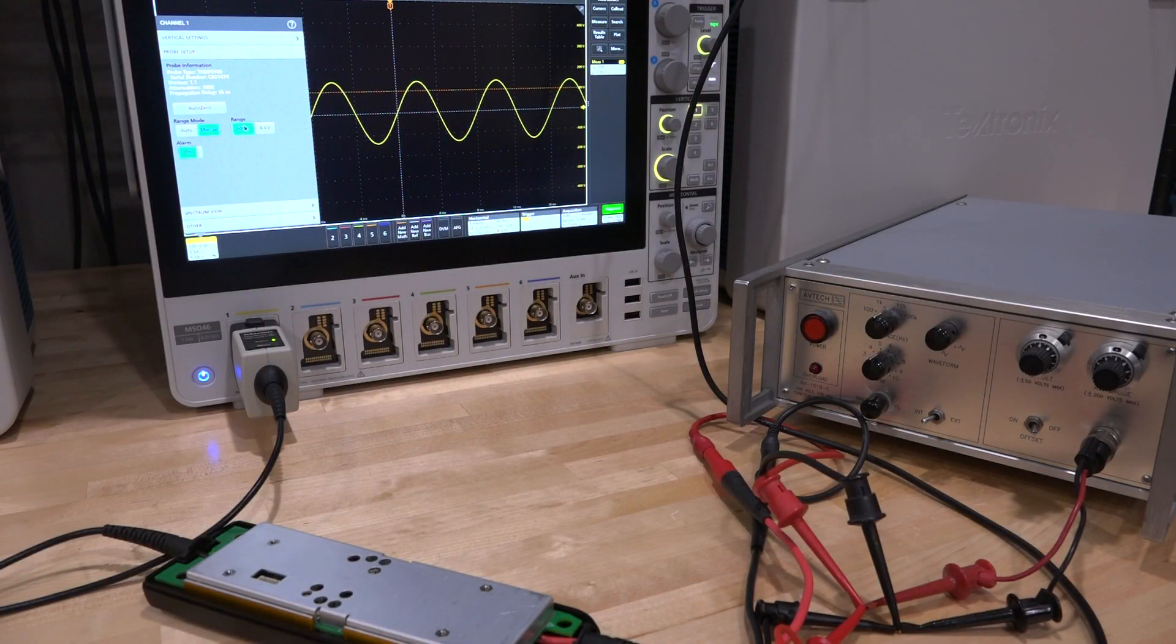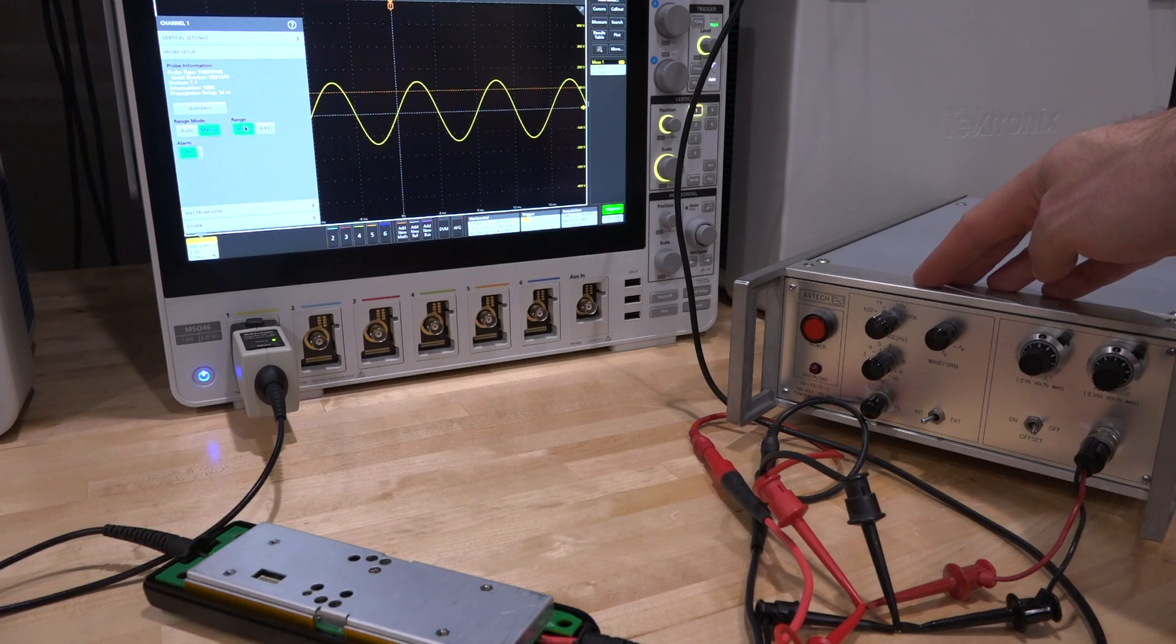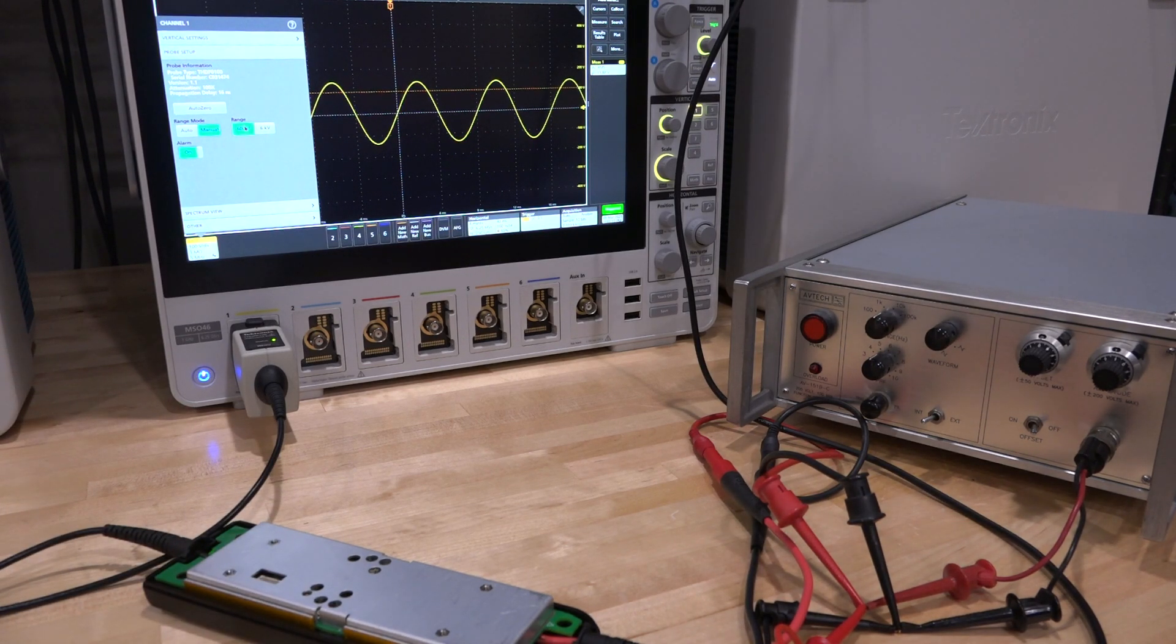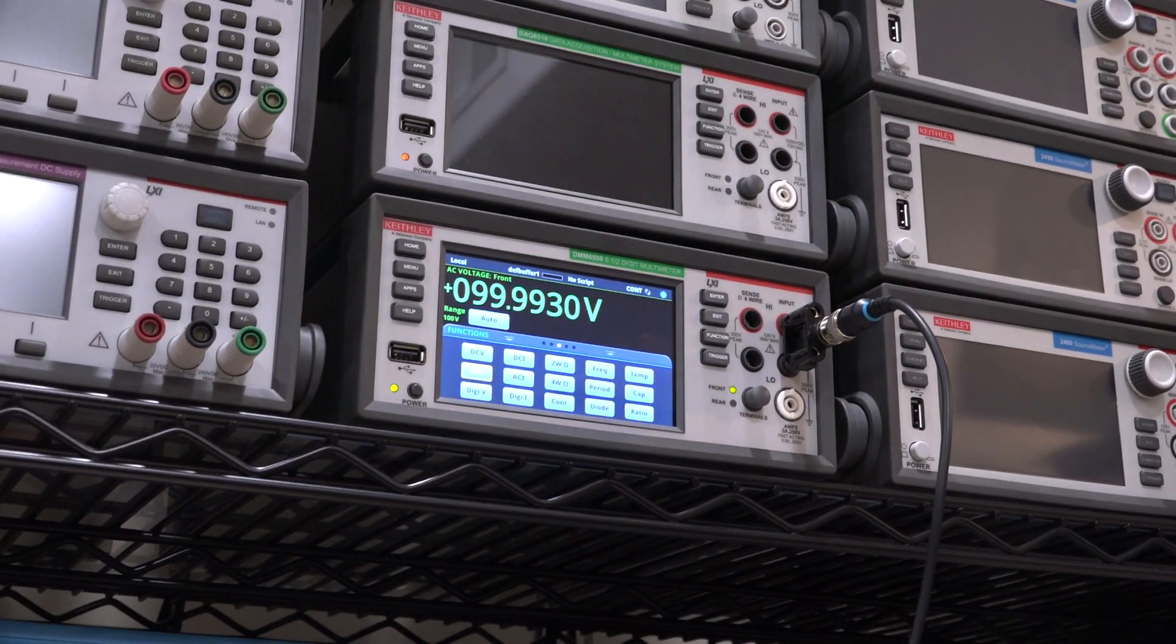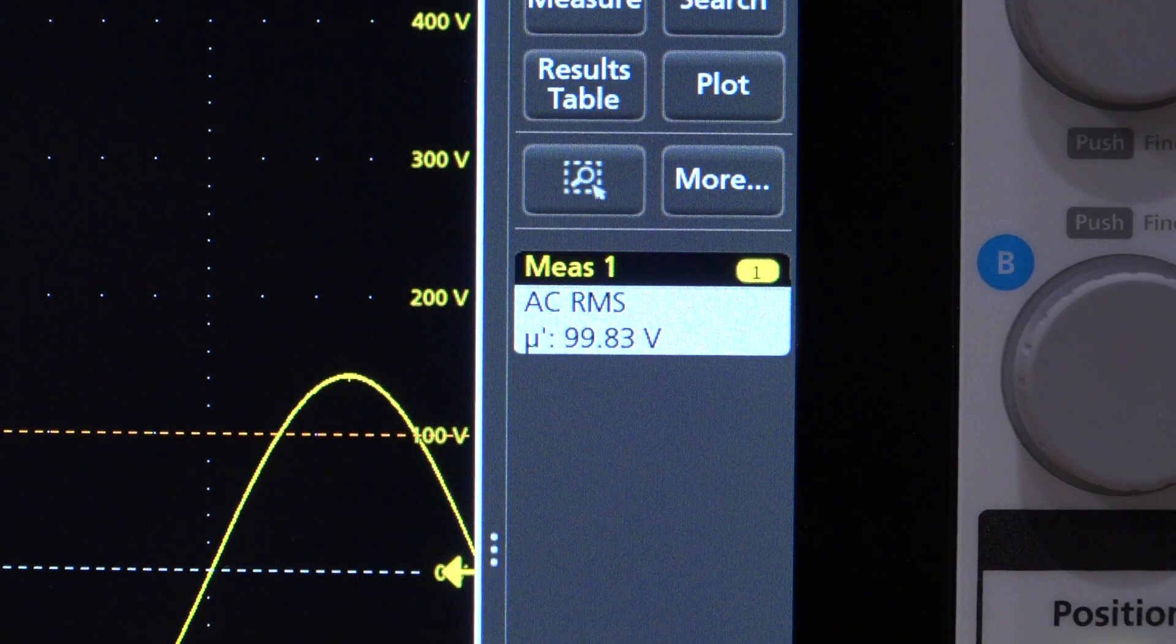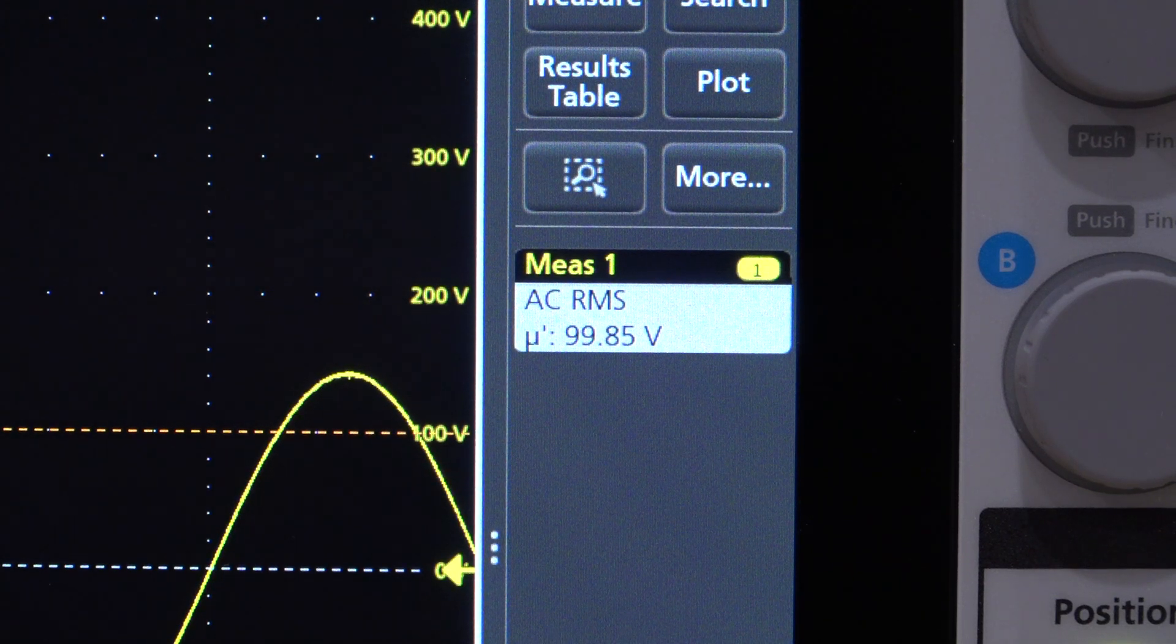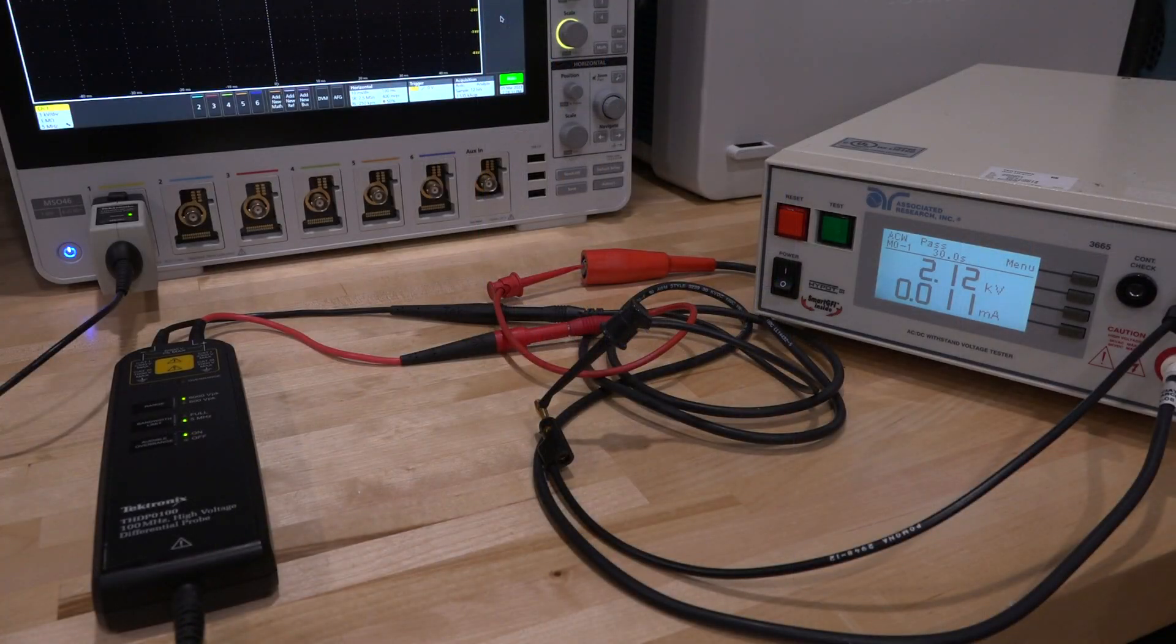Now we should just zero it and do a quick calibration measurement on it to make sure that it is actually functional all the way from the inputs to the probe head. So I performed a very crude calibration. I used a high voltage function generator here that can go up to a couple hundred volts, and it allows me to put in a precise, let's say, 100 volt RMS signal and then measure it with the probe. There are two potentiometers on here, you can adjust the gains at the two settings, and you just want that measurement to agree with the multimeter. The multimeter is measuring RMS voltage, the scope can calculate RMS voltage, and then from that we can adjust it until we get the right value. You can see how close the value is - this is in the 600 volt range and the 6 kilovolt range. It's almost exactly the same.